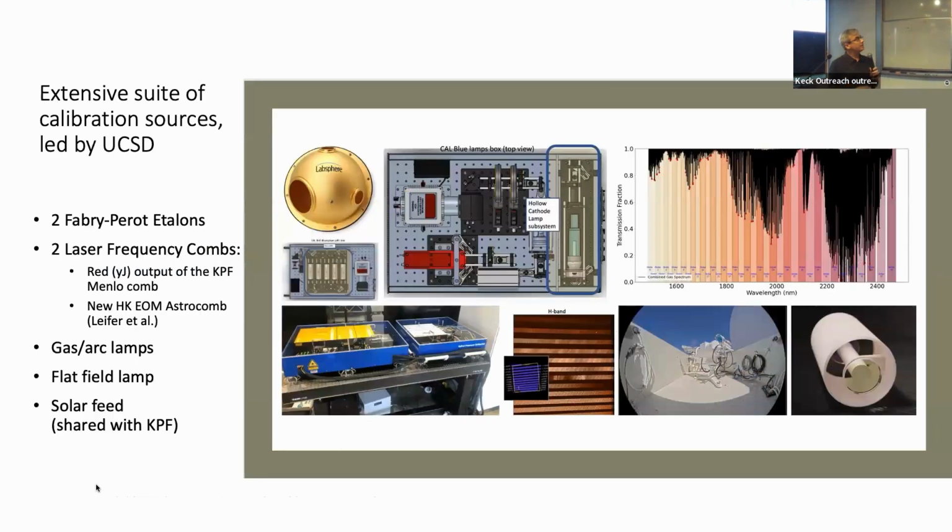UCSD is leading the calibration subsystem. They passed their manufacturing readiness review. There'll be multiple modes of calibration, including the laser frequency combs at Keck, as well as Fabry-Perot etalons, gas cells, our hollow cathode lamps, flat fields, et cetera, and the solar.